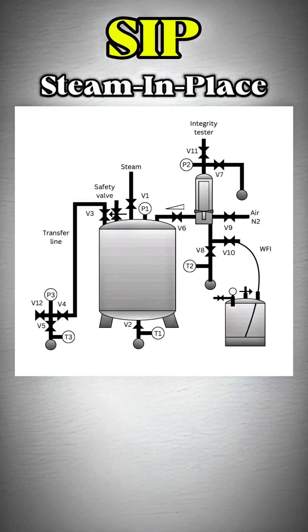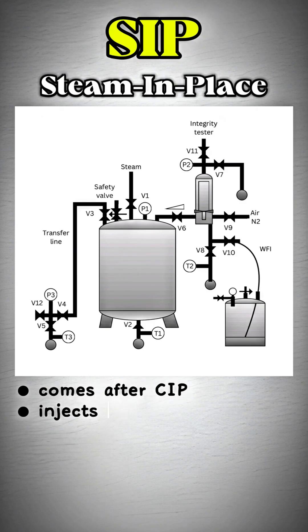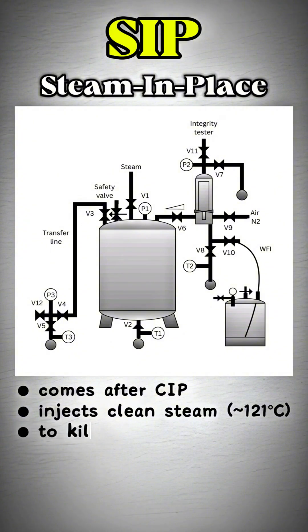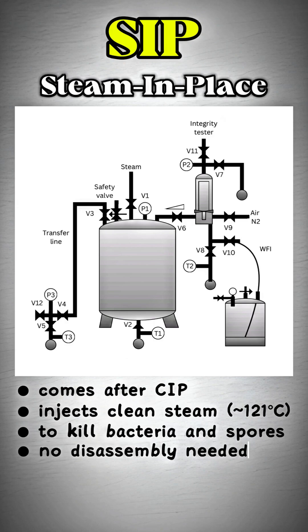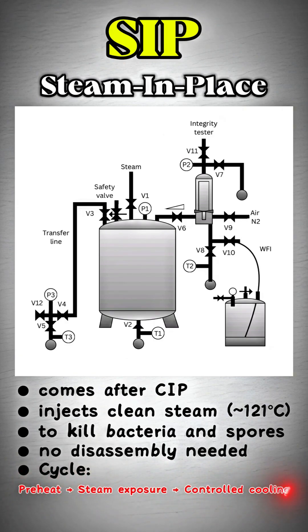SIP: Steam in Place. Steam in Place comes after Cleaning in Place. It injects clean steam — approximately 121 degrees Celsius — to kill bacteria and spores. No disassembly needed. The cycle: preheat, then steam exposure, then controlled cooling.